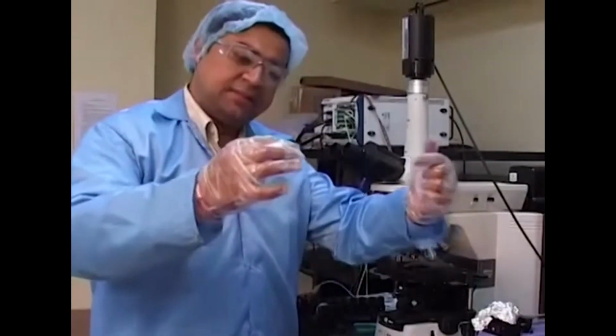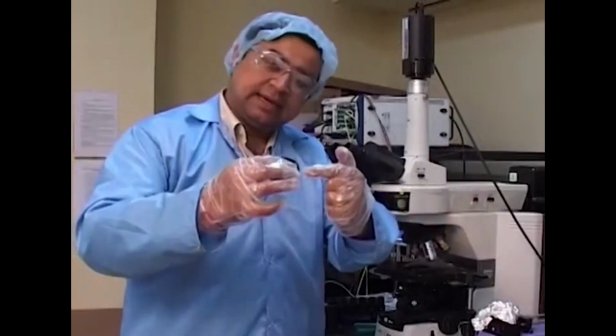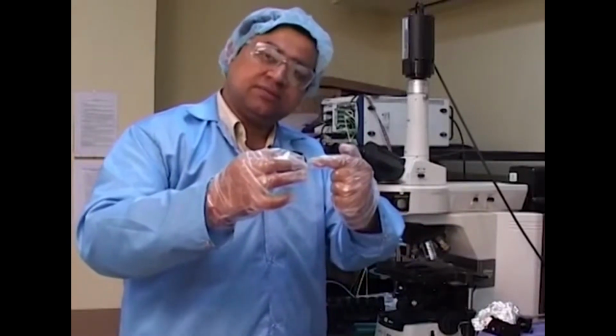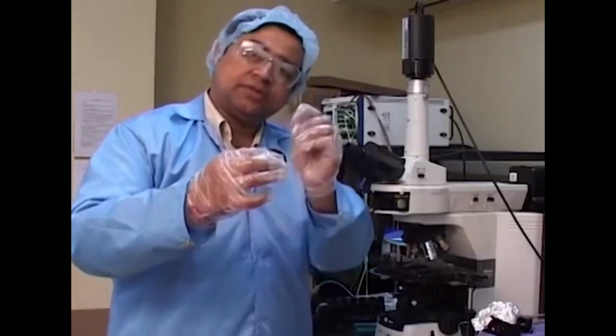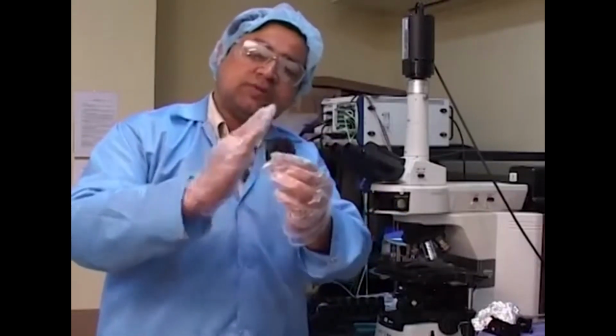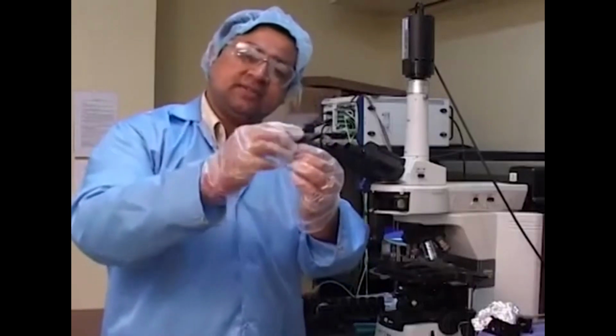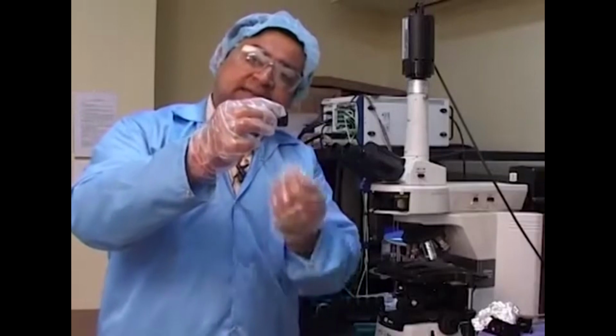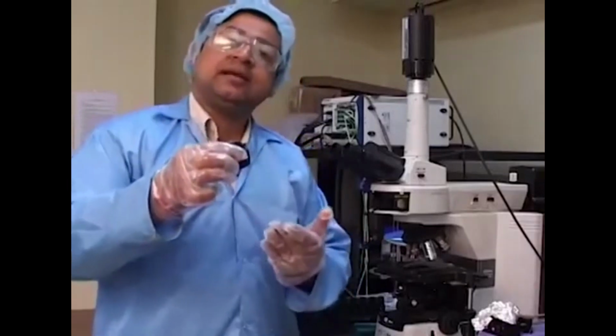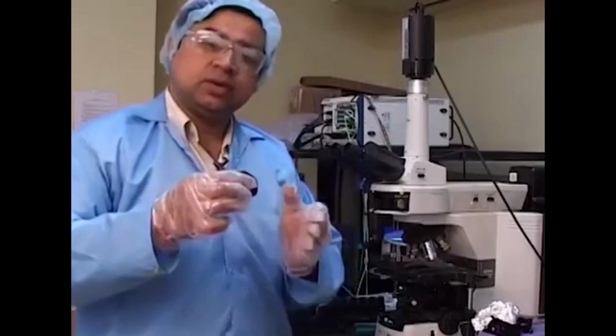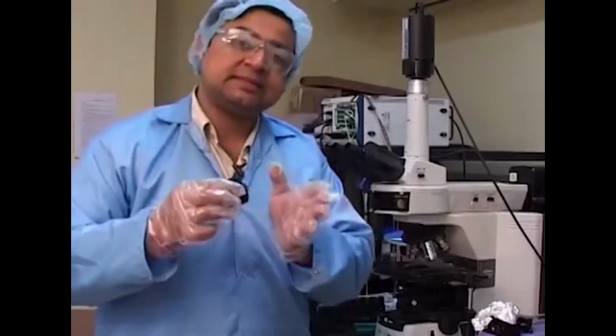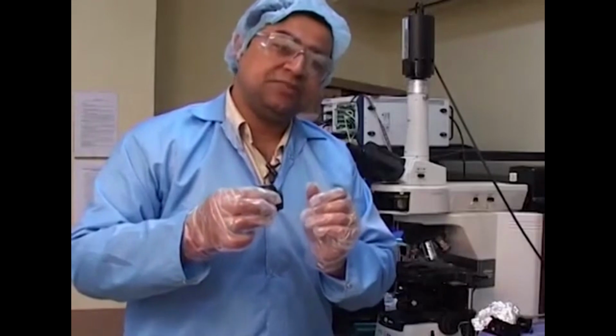Okay. So you have a light beam coming from this end, cutting a portion of it through the filter, and then the cutoff portion, which is the necessary portion, goes and falls onto the 45 degrees mirror, which is placed in the center of the cube, and it gets reflected by the mirror, because that's the property of the dichroic. Okay. So let's say we are trying to cut off a 390 plus minus 10 nanometers wavelength band. So essentially we use a filter so that the package of light which comes out of the filter is from 380 to about 400 nanometers.